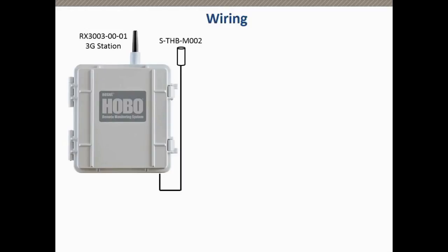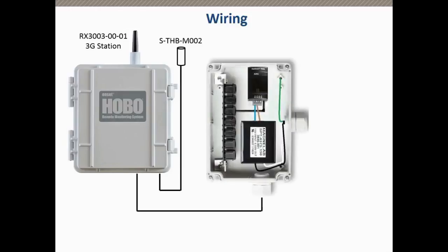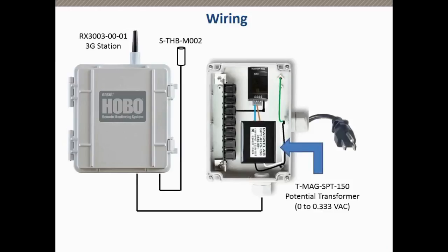We have an STHB temperature and relative humidity sensor attached. The voltage monitoring circuit, we put in an external enclosure. This is the size enclosure you would typically use. We use the smaller one because of the space constraints, but either one would work for this application. We used the potential transformer, the SPT150, to monitor the voltage. That was connected to a line cord. Of course, you want to be wiring this per local electrical code. This is in an enclosure, so it's protected, and we have that plugged into the outlet that's near this device.